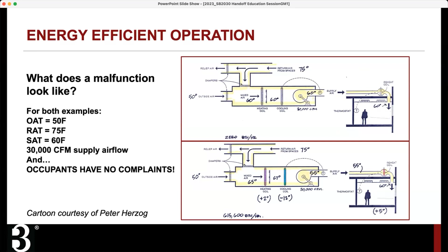Now, in the first case, because everything's functioning correctly, you're expending 0 BTUs per hour of heating or cooling energy. By contrast, in the bottom case, with the heating coil being slightly activated, the cooling coil overdoing it, and then the reheat coil adding 5 more degrees at the end, you're burning 615,600 BTUs per hour, all while the occupants have no idea that anything is going wrong, nor does the building operator unless they actually go look for this malfunction. So again, the goal is to ensure that each significant energy consuming device uses only as much energy as necessary to perform its intended function.